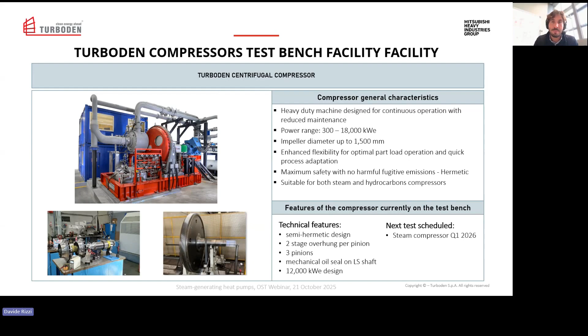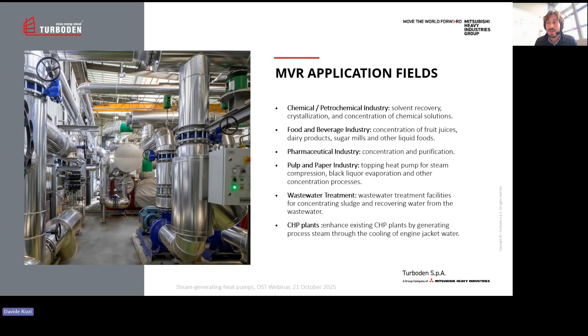Regarding applications of the steam compressor, I think the previous speaker already touched on those points, and this is good because it means we are aligned and there is a real need within these sectors. We see applications for steam compressors, both heat pumps alone or heat pump plus MVR, in chemical and petrochemical industry, food and beverage, pharmaceutical industry, pulp and paper, wastewater treatment, and last but not least combined heat and power plants, where jacket water can be valorized using either a heat pump or a steam compressor, because the evaporation temperature level is still good enough to allow good efficiencies.